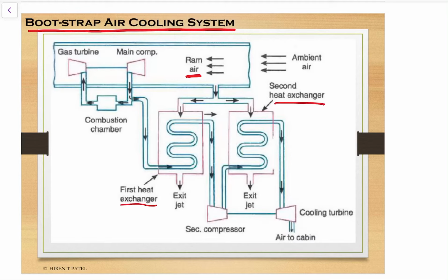The difference is that a secondary compressor is introduced between the two heat exchangers. So air passing from the first heat exchanger does not go directly to the cooling turbine, but first passes through the secondary compressor where it gets compressed and the pressure rises. Then it passes through the second heat exchanger where it gets cooled, and then passes through the cooling turbine.